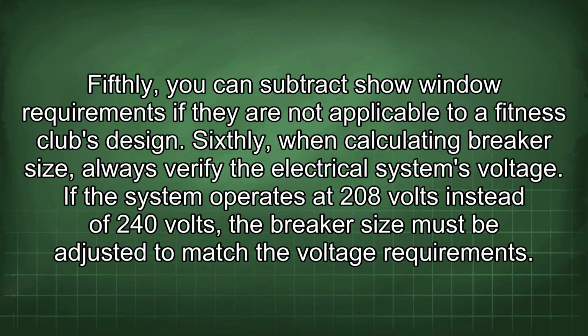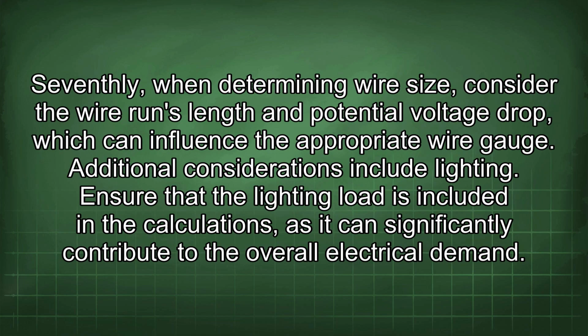Fifthly, you can subtract show window requirements if they are not applicable to a fitness club's design. Sixthly, when calculating breaker size, always verify the electrical system's voltage. If the system operates at 208 volts instead of 240 volts, the breaker size must be adjusted to match the voltage requirements. Seventhly, when determining wire size, consider the wire run's length and potential voltage drop, which can influence the appropriate wire gauge. Additional considerations include lighting.